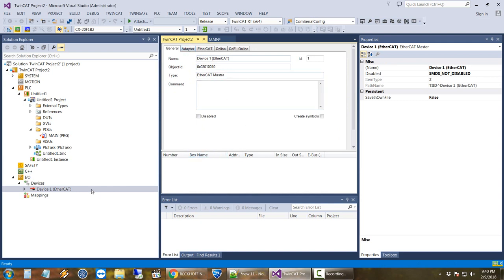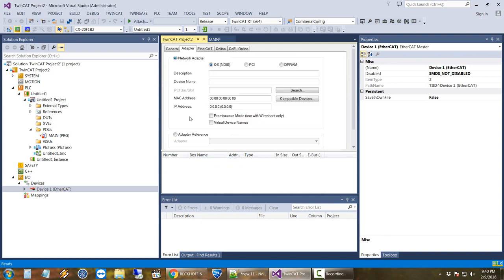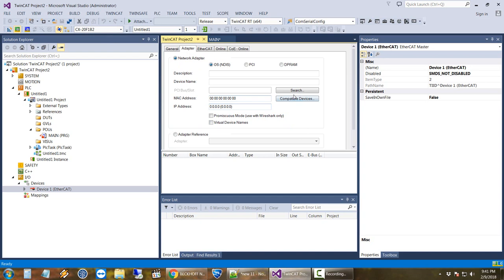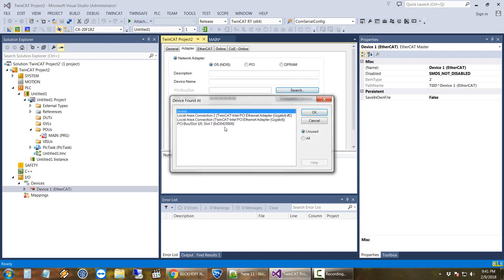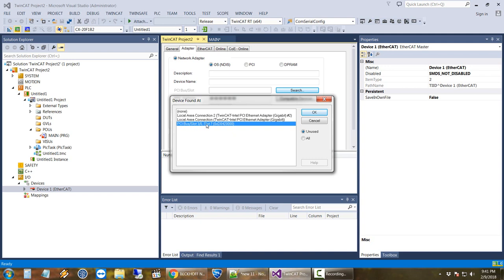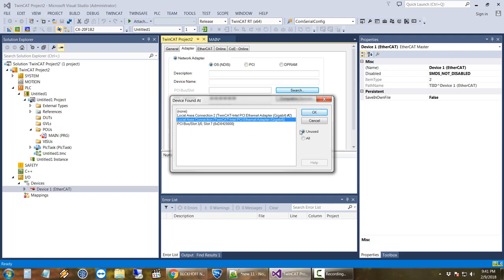So I'm going to add that guy in right now and open him up. And right off the bat, he hasn't been assigned to any hardware. He doesn't know really what he's looking at. So we need to go tell him, hey, you need to be bound to that bottom network card that had the yellow cord coming out of it. So we'll come over here and when I'm connected up, I've got this PLC targeted here. So I'm actually talking to it kind of in context of that PLC. So I'll come here and I'll say search for devices. This PCI bus slot is actually the e-bus going off that right side that I kept pointing to. So we're not going to mess with it right now because I don't need to talk to any of that I.O. We're setting up the stuff that's coming off of that other NIC. So this will actually end up being its own EtherCAT master on the system. This one here, I'm going to just guess basically, local area connection. I normally like to name these on the PLC.